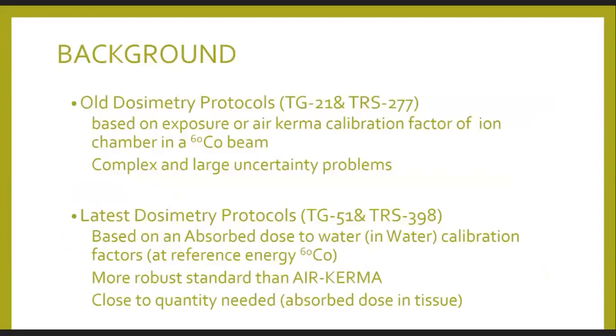That quantity is the absorbed dose in tissue. So it requires many correction factors, many conversion formulas to convert the air kerma calibration factor to absorbed dose to water.